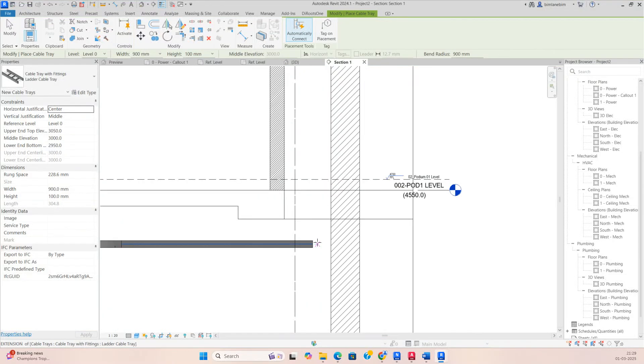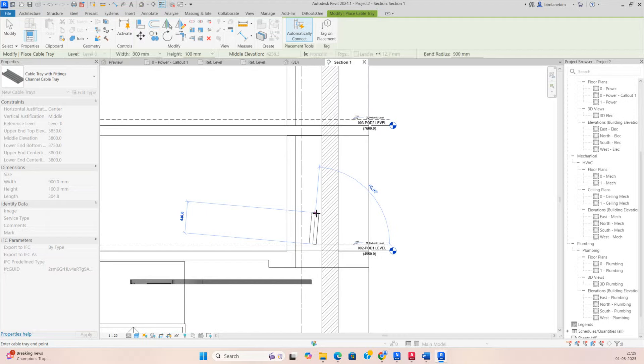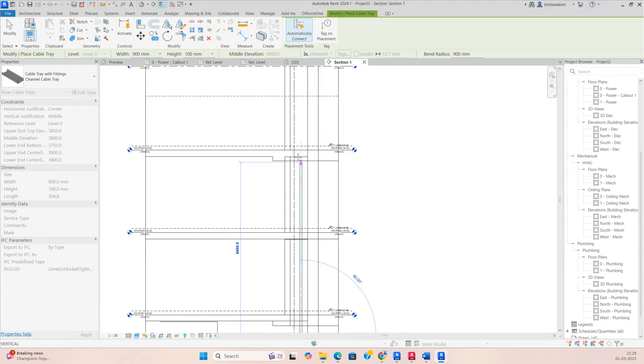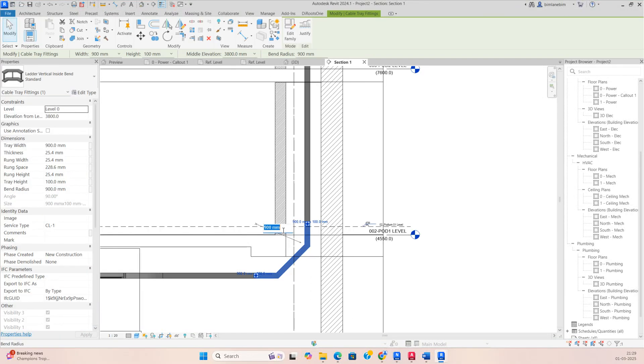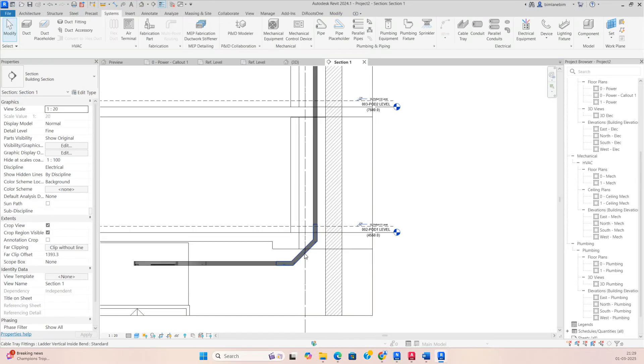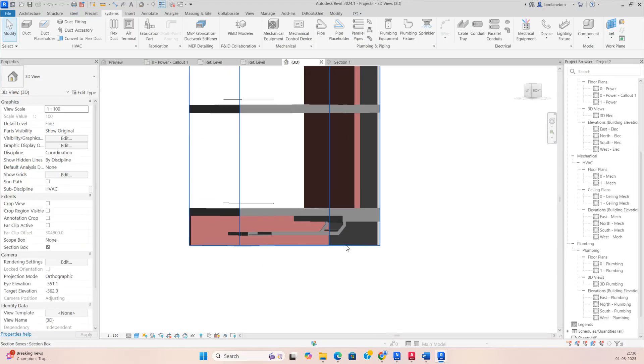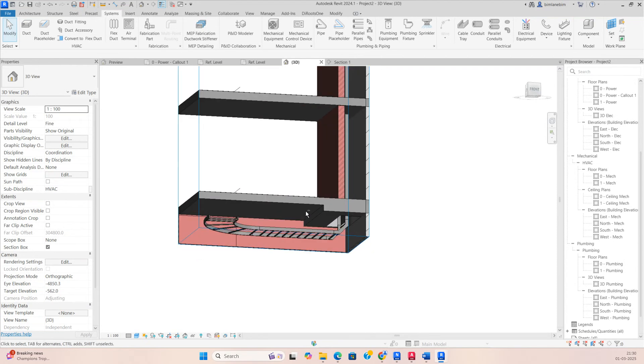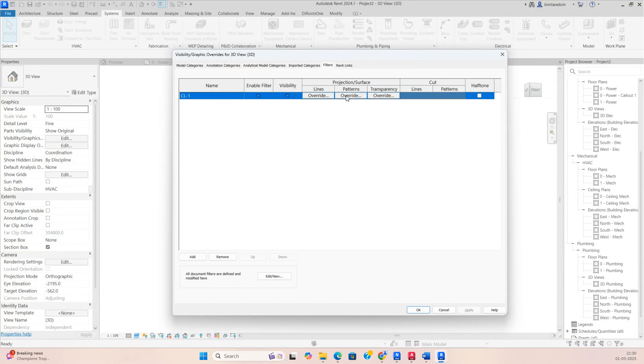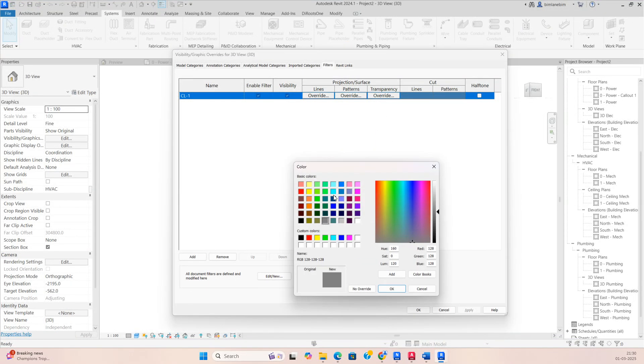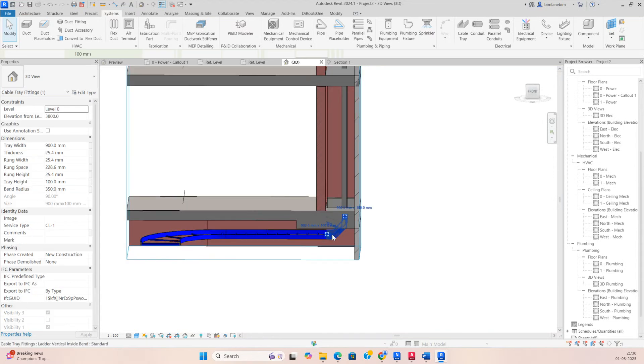Run the channel cable tray from this point to where it's required. Set the bending radius to around 350mm. In the 3D view you can see the cable tray connecting to the ladder and going up. Apply the same filter with blue color and solid fill, set the service type to CL1, and you can clearly see the cable going up to the opening.